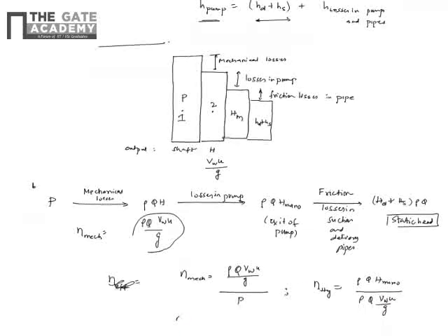That is hydraulic efficiency. And then basically the hydraulic losses in the friction outside. So this is hydraulic efficiency in the pump, this is hydraulic efficiency in the pipe. So that is the static head by your rho Q manometric. So most of the time we don't segregate this, but I have just explained. So the overall efficiency is the power associated with the static head, rho Q static head, by the shaft power.